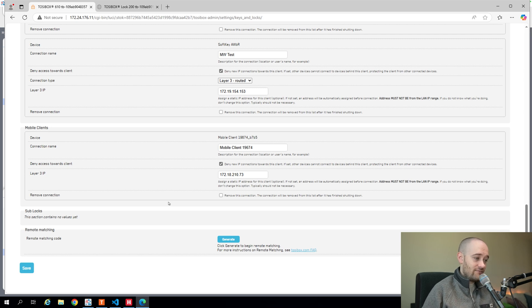You don't need to do this unless you have a specific reason to. I would definitely say to stay at the Layer 3 default unless you have a specific need — whether it be BACnet IP or some other communication that requires broadcast traffic to pass through. Thanks for watching. If you have more interest in this kind of networking-specific stuff, check out our Networking 101 series — nothing has really changed in networking fundamentals, so it's still very much viable. Like and subscribe if you haven't already, and if there's anything specific you want to see related to networking or BACnet IP — maybe BBMD, which would let you do this in a Layer 3 scenario instead of switching to Layer 2 — leave those in the comments below.